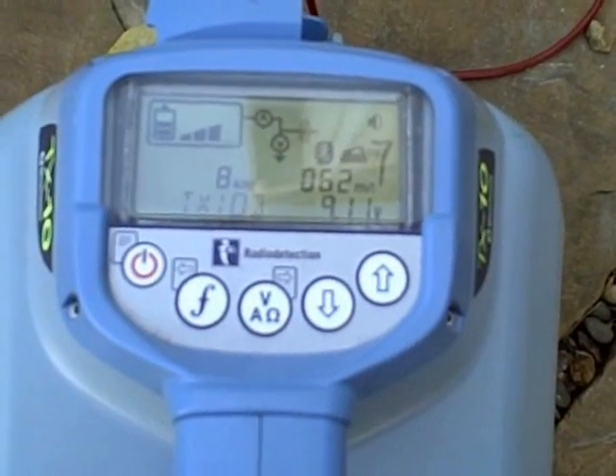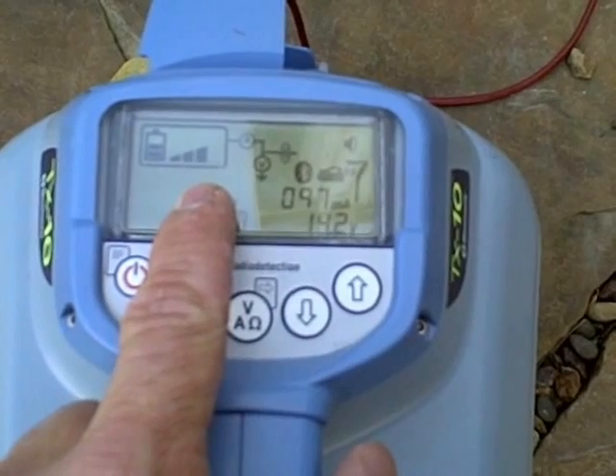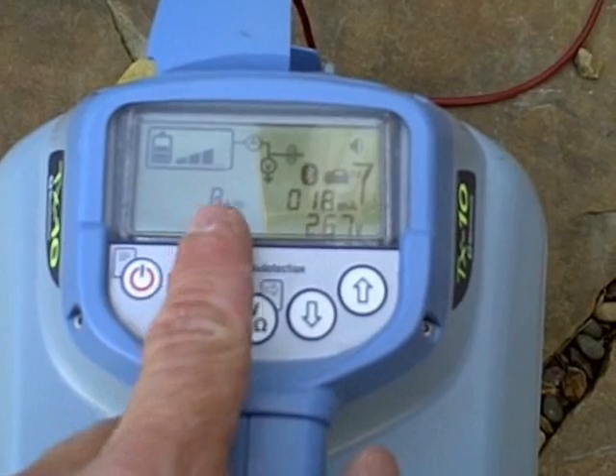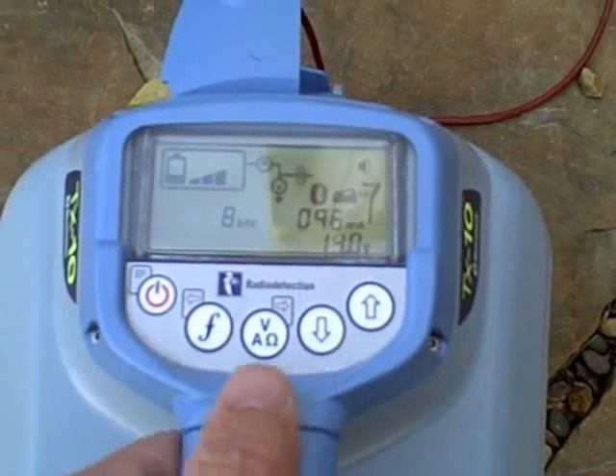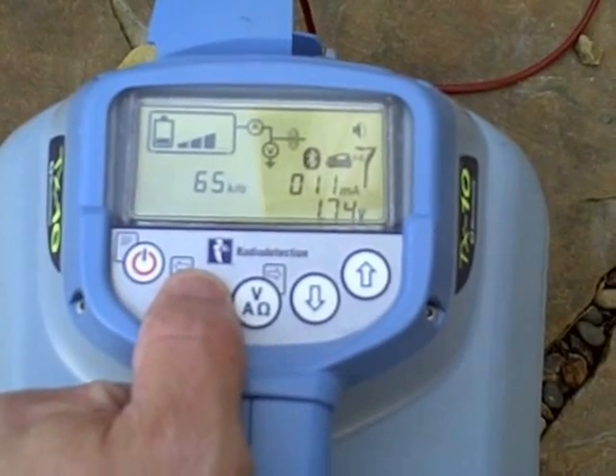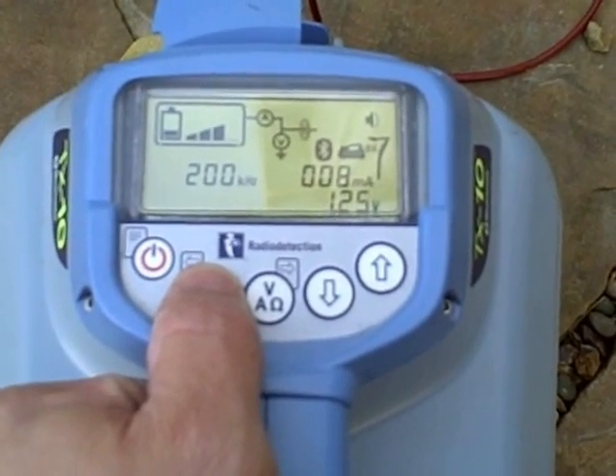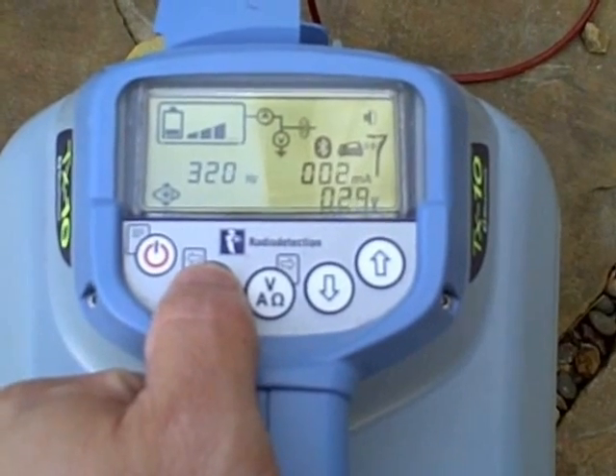The transmitter has a backlit LCD screen. It displays the battery life, the output level, the milliamp reading, a voltage reading, and the frequency that you're applying. You can select the frequency by hitting the F key on the keypad. Each TX3 and TX10 transmitter comes with 15 possible active frequencies. Eight are induction frequencies. Fault find mode is also an option.